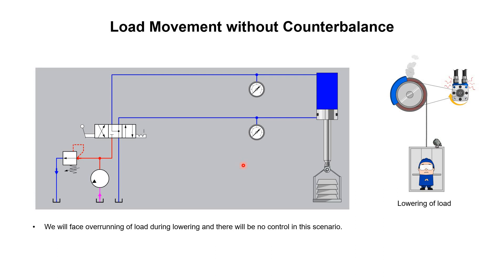A similar situation is shown in this hydraulic circuit, where this cylinder is being used for the raising and lowering of a load. Here we have a direction control valve. If we want to raise the load, we change the direction. From the hydraulic pump, fluid will move in the selected direction, come to this point, and start moving the hydraulic cylinder upward — so we will be able to raise the load. This is a normal operation.